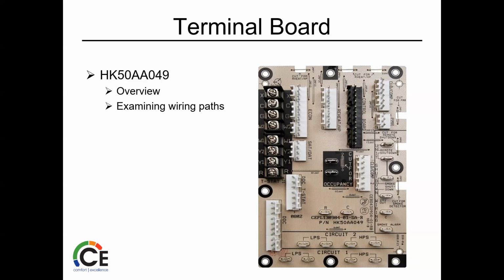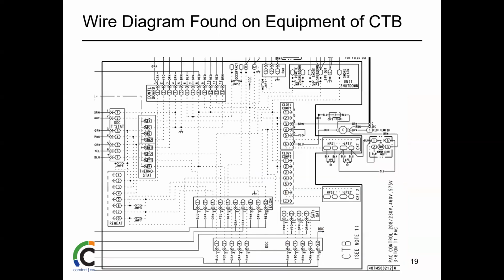If you're doing any kind of building management control, that's where DDC comes in. Control board, which is your main bus. If we're dealing with any kind of reheat or a heat pump, you've got a Molex for that there. Occupancy cutoffs. Then of course, low and high pressure switches for both circuits if it's a two-stage or anything in that line. So really basic wiring data here. So that's basically just the board.